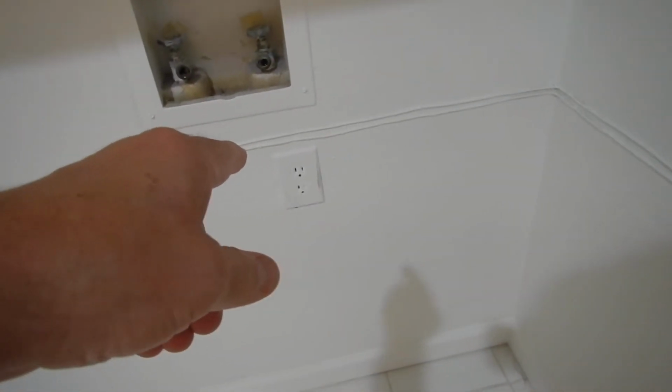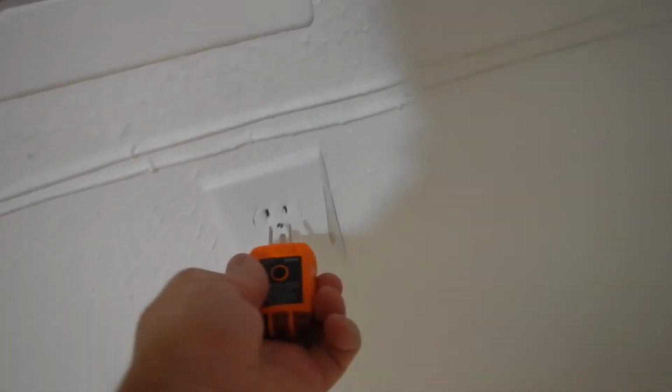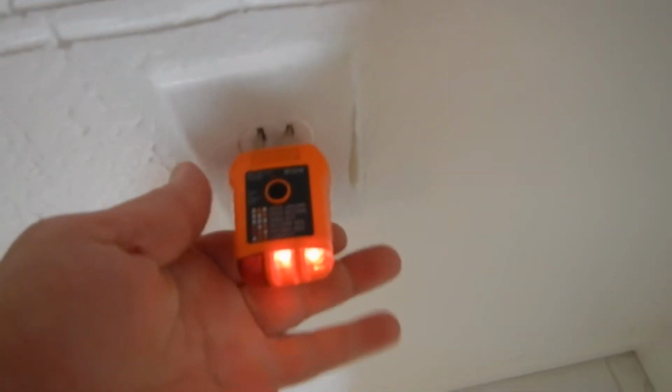But we can try. There's a 3-prong clothes dryer outlet. It's not GFCI protected. It wasn't required when this home was built, by the way. But by current standards, it would be GFCI protected. This 120 should be GFCI protected. They painted over it. I got in there just enough to test it, but whoever's going to install your clothes dryer, you're going to have trouble installing this. That's as far as I got in. I didn't plug it in right.